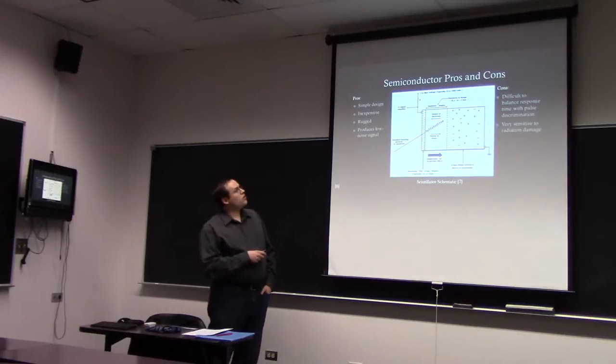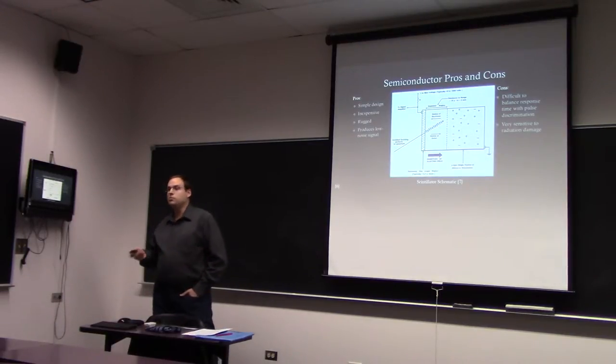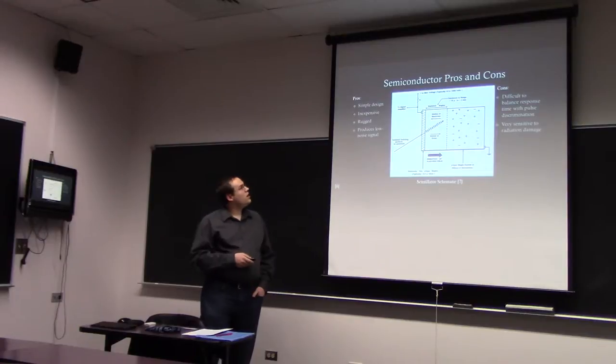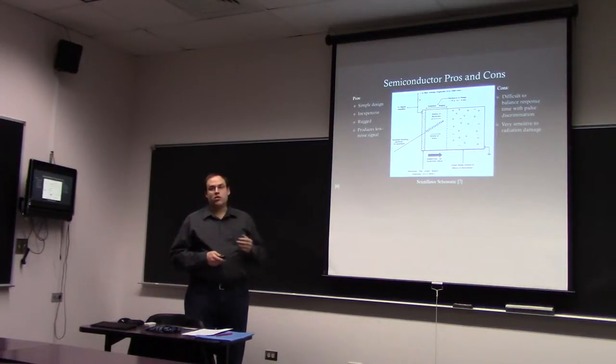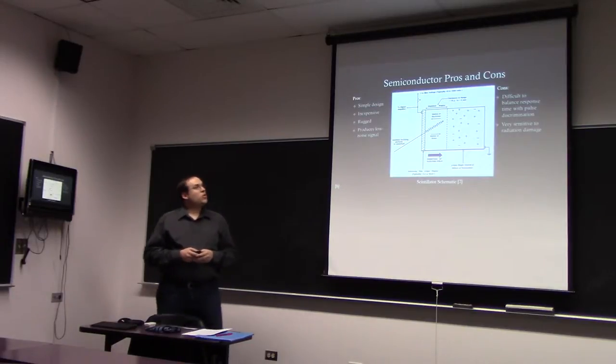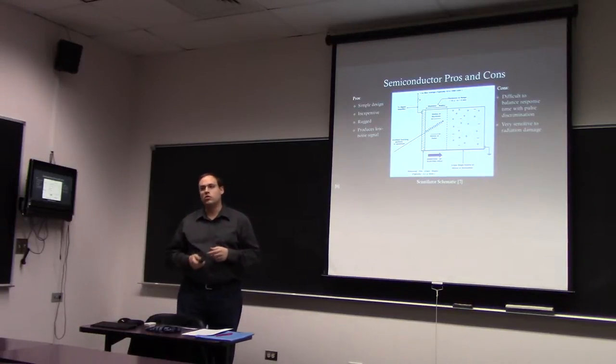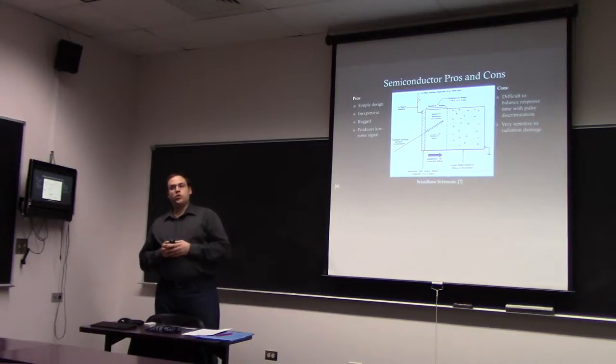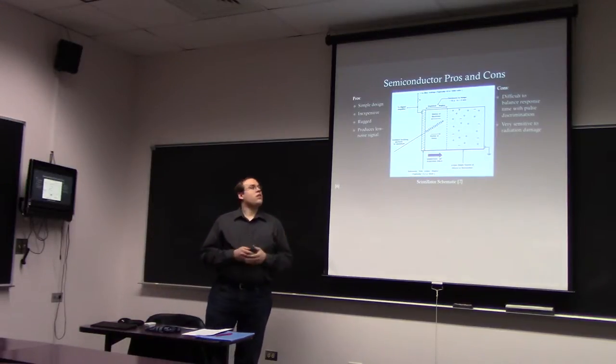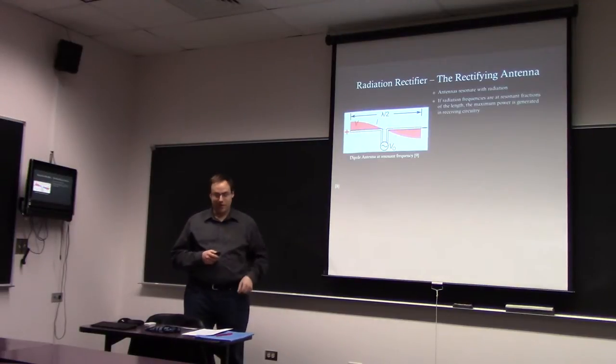The good thing about these is they're nice, simple devices. They're relatively inexpensive, and they're much more rugged than typical scintillators. And because you're already dealing on a semiconductor level, you tend to get much less noise when you amplify it, because you just pass it directly into a preamp, which you can play with quite a bit. However, it's extremely difficult to balance response time with discrimination, so if you're looking for something that can quickly identify incoming radiation, you tend to not be able to spectrally identify it very well, and then the reverse is also true. They're also very sensitive to incoming radiation damage, because they're relying on very small impurities.